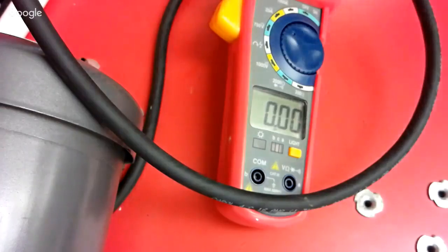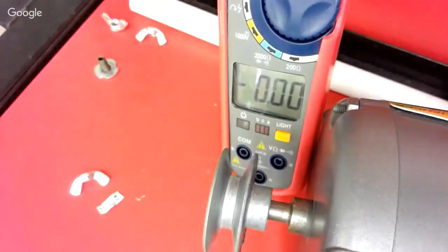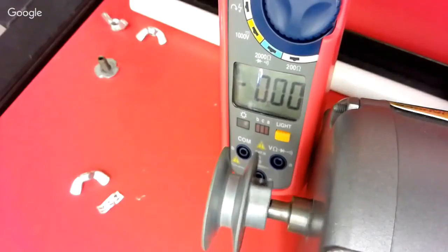We'll read something on 2 because we have one of them that's not canceled out. I'll read slightly less than what I should, but when I have all 3 of them encapsulated inside the little coil on the meter, I read nothing because they cancel them out.